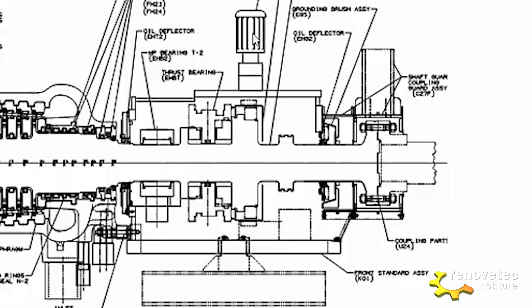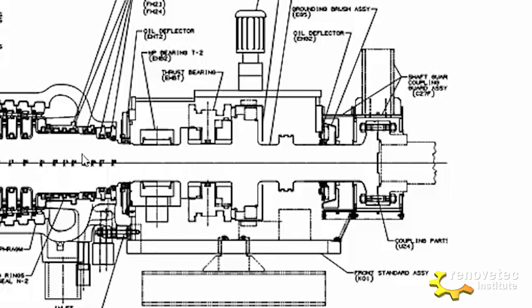Remember that in the previous video, the turning gear avoids the bending of the rotor when the turbine stops and the turbine is hot. The turning gear is coupled to a disc here, connected to the collar. And all this part — all these elements — is the thrust bearing, which tries to avoid the movement of the shaft in the axial axis.